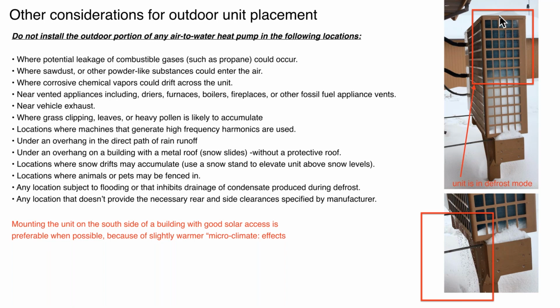Most of this is common sense, but we put this down here to keep you thinking about where to put that unit. And I put down here at the bottom, all other things being equal, if you can put the unit on the south side of a building, you are going to benefit from what we call a slight microclimate effect. The air is going to get a little bit warmer on the south side of that building when the sun is out during the day, and that's going to give you some benefit in terms of heating performance. Okay.